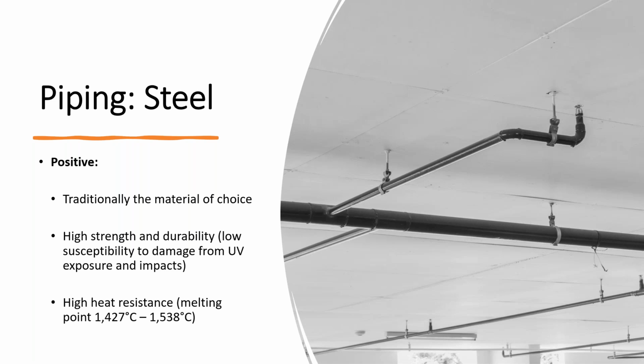When it comes to steel pipe, it has traditionally been the material of choice for fire sprinkler pipes because of a number of things, including its strength, its durability, and its high resistance to heat. So when there's a fire, the steel pipe can resist the heat being produced a little bit better than the plastic pipe can. Again, like we're saying, the high melting point of the steel means that even when it's subject to very intense heat from the fire, it will maintain the flow of water to it.